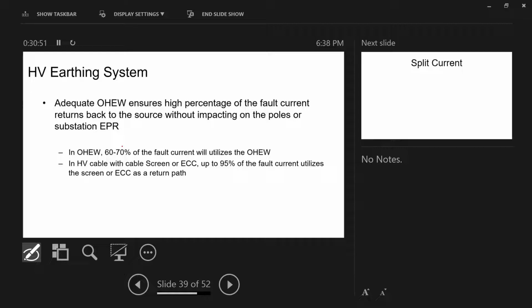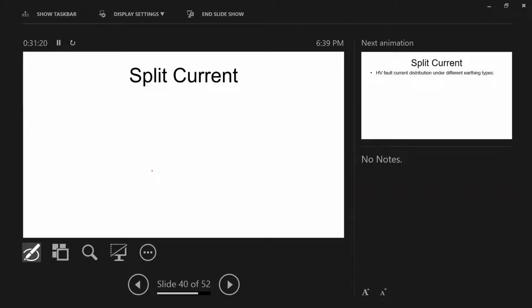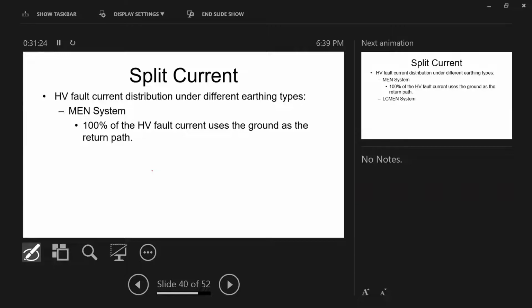If you have a cable screen, or earth continuity cable, this ECC, because the cable screen is very close to your conductor, could be a couple of centimeters, the mutual impedance will be very high. This mutual impedance will force a current, it will create like a vacuum. When the current hits the ground, it will vacuum through the cable screen, could be up to 90, 95, 96, 97%, depending on the soil resistivity around it. Now, in these last few slides, I would like to show you that in reality, when it comes to the system, it's good to know what an MEN, main earth neutral system, is. The main earth neutral system, 100% utilizes the current into the ground.